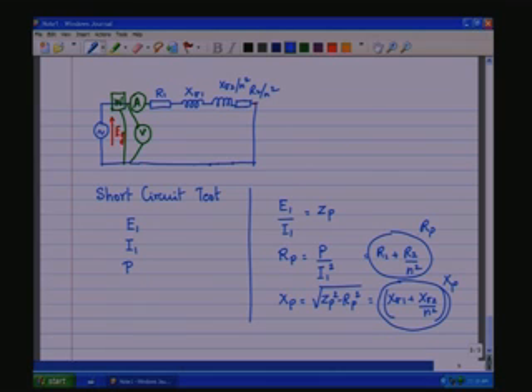As N is known, one can also find out the other parameters. R1 can be measured directly knowing the number of turns, or measured directly from a multimeter, then R2 can be found knowing N, and in this case we have to take this as an equivalent secondary leakage or the primary leakage as seen on the primary side. So, with this we know about the transformer, equivalent or complete equivalent circuit, the phasor diagram, how to analyze it, and then what are the parameters that come into the imperfect or the practical transformer.